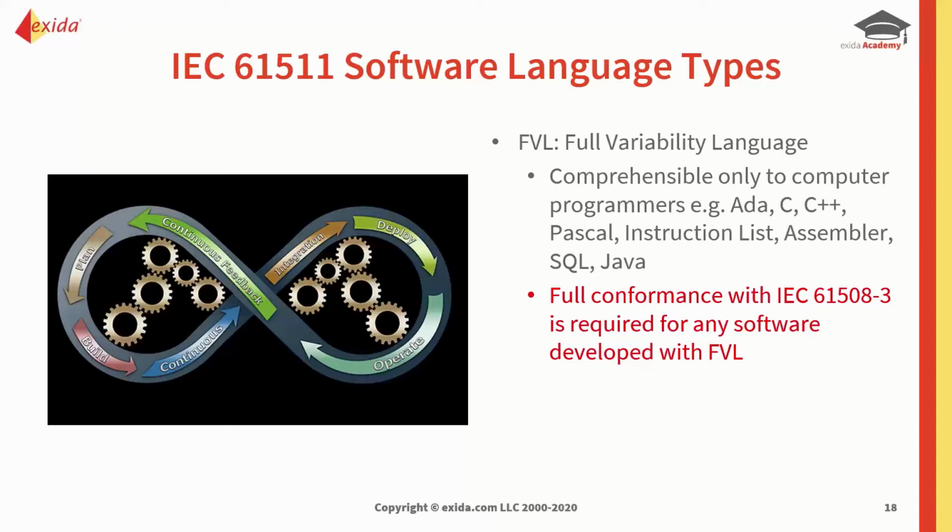And the trouble is with software engineers, they love to reinvent the wheel. They all think that their software is better than anybody else's. And in some instances, that may be true. However, they cannot be allowed a free hand to go and write specific particular application function blocks or algorithms using FVL unless it's properly within the confines of 61508-3 for the specific SIL. So this is something that's very important.